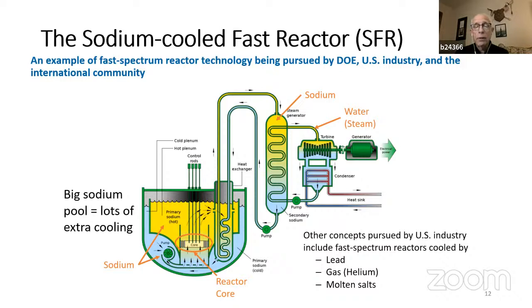And so we have to have a very large, robust steel system, a big vessel that contains all this stuff in a water-cooled reactor. We don't need 8 or 9 or 10-inch thick steel vessels for a sodium-cooled reactor because it's atmospheric pressure. So we can get by with something on the order of an inch, which is a lot cheaper. That means we can make it really big and we can immerse the entire reactor and its cooling system in this vessel that doesn't have any penetrations in it for cooling loops and all that other stuff. So there's no leakage path out of it.